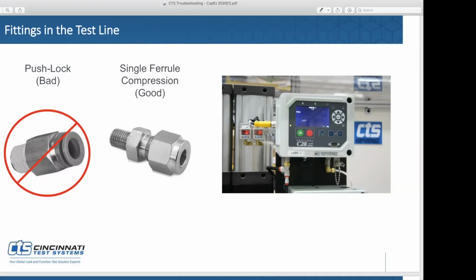Also, use the right types of fittings, MPT fittings with either Teflon tape or Swagelok. We've really migrated a lot to Teflon tape rather than using the sealant because of the gooiness of it. Really? Yeah. I remember, and my apologies for taking us back in time, some of the challenges I had with piping that customers would do was because they would get the Teflon on the tip, and it would actually end up in one of my valves. So that's the caution of using Teflon tape: when you wrap it, make sure it's not wrapped over the end, and you allow some thread grip and then start the tape. So that's some of the keys to using it.